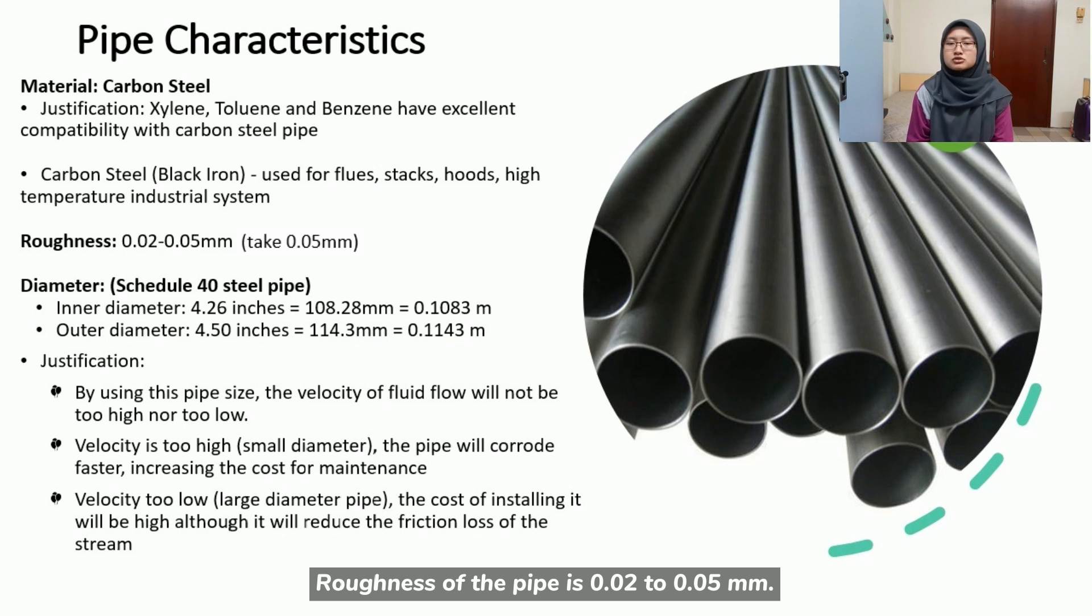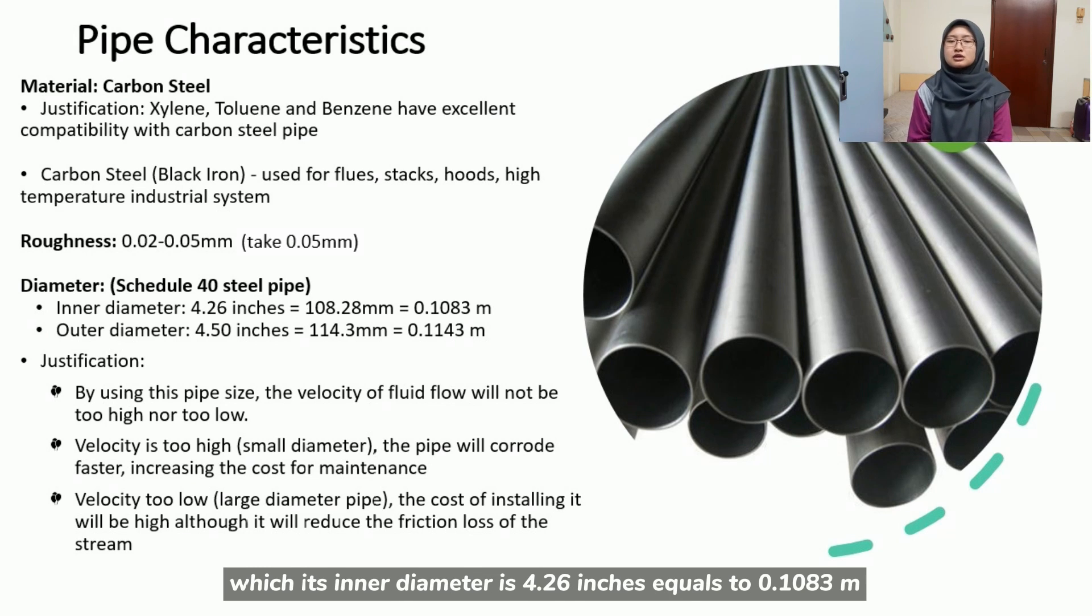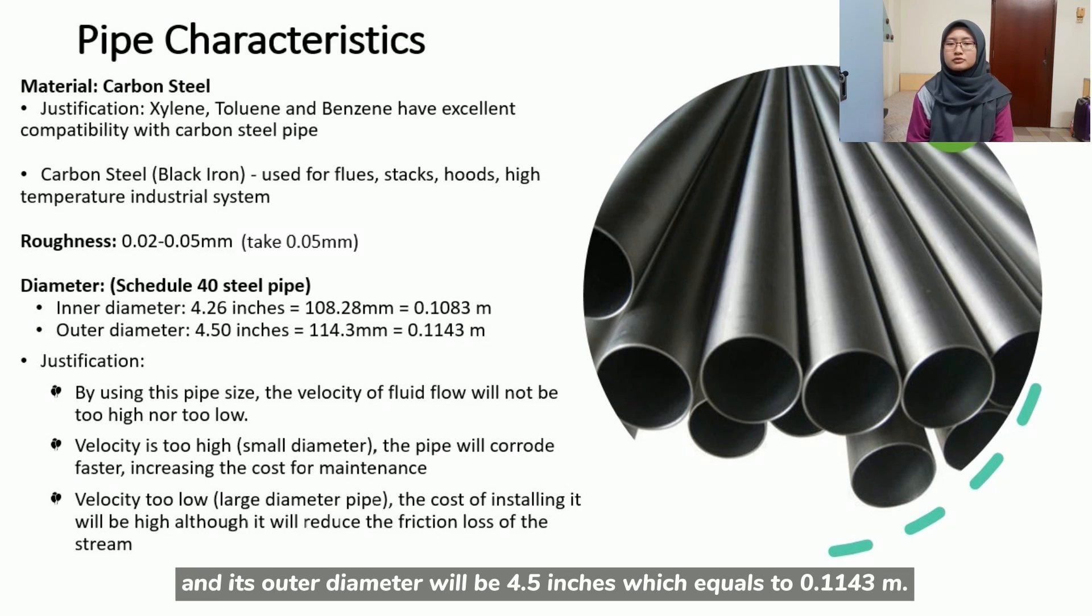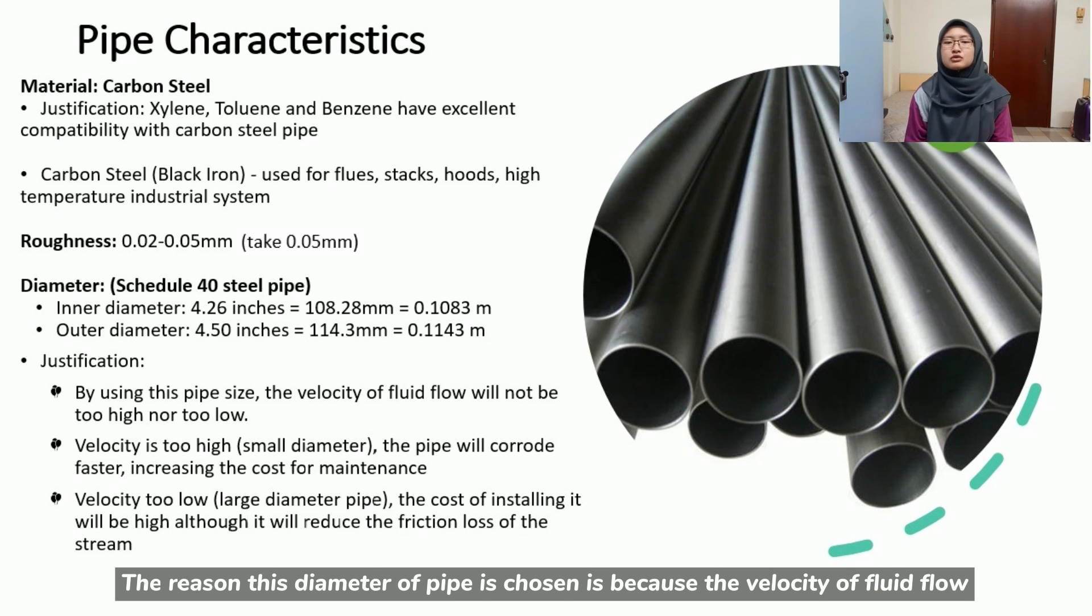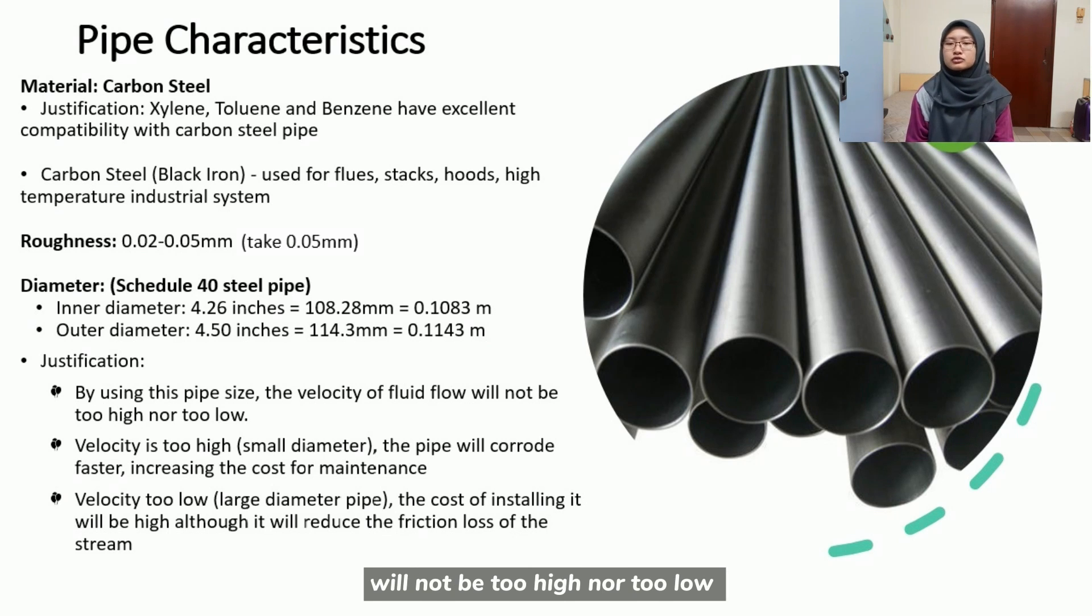Roughness of the pipe is 0.02 to 0.05 mm and we assume it to be 0.03 mm. Diameter was based on the schedule 40 steel pipe. We picked the 4 inch pipe which its inner diameter is 4.26 inches equals to 0.1083 meter and its outer diameter will be 4.50 inches equals to 0.1143 meter. The reason this diameter of pipe was chosen is because the velocity of fluid flow will not be too high nor too low.